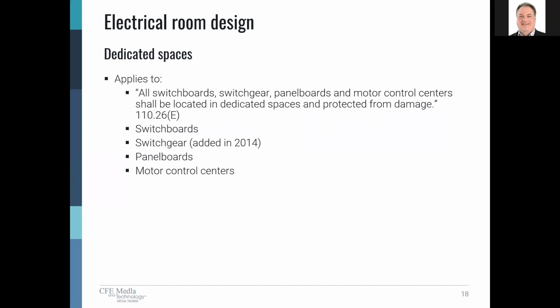So let's return a little bit to dedicated spaces, which we touched on, and move beyond working space. Dedicated spaces, again, applies to all switchboards, switchgear, panel boards, motor control centers, shall be located in dedicated spaces and protected from damage. This obviously includes switchboards, switchgear, which was added in 2014, and James talked a little about the differences switchgear have, and we'll talk more about that later in the presentation, panel boards, and motor control centers.